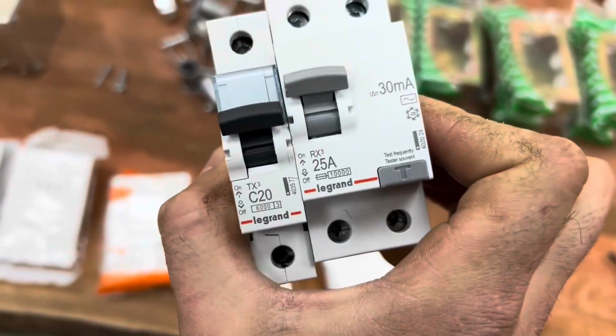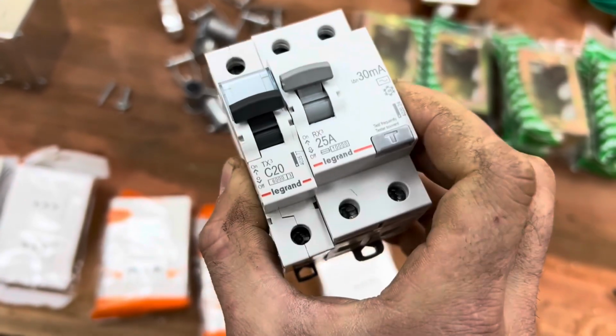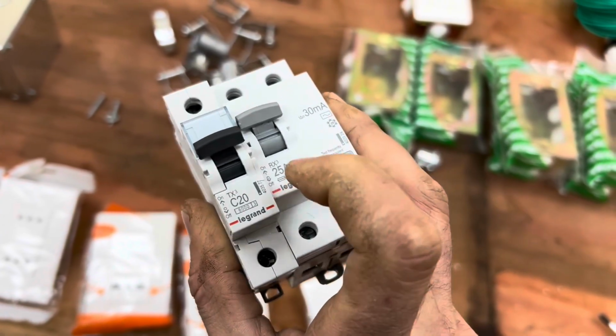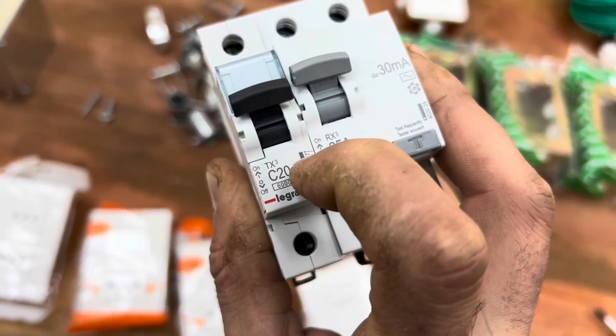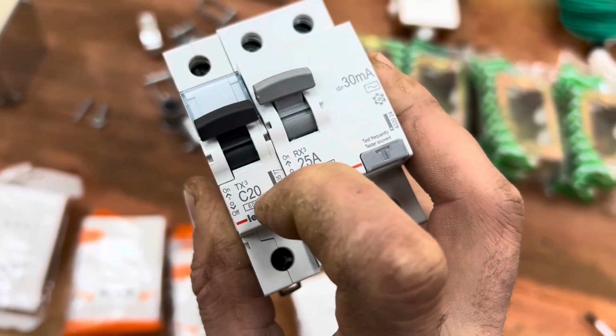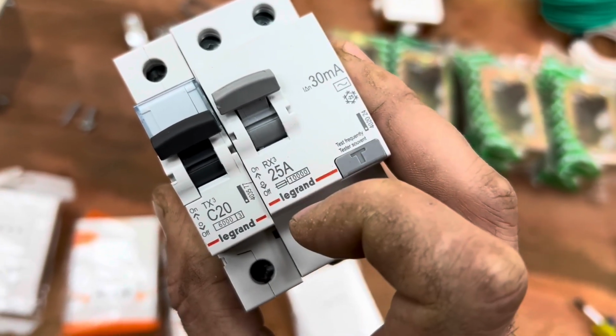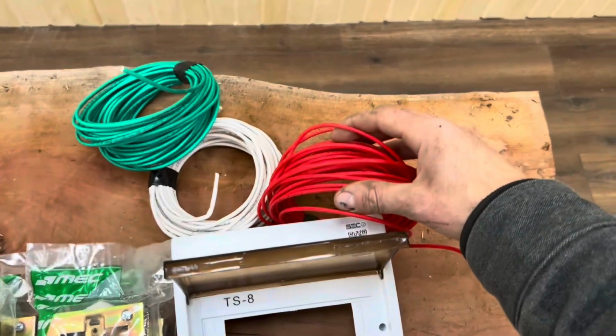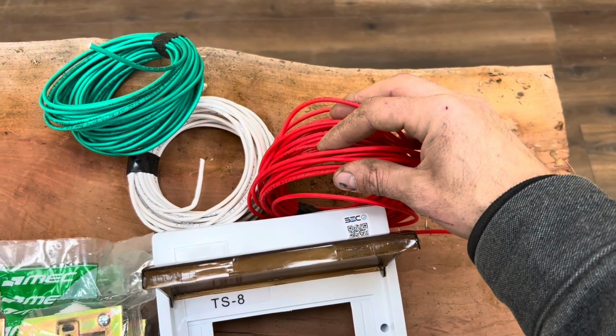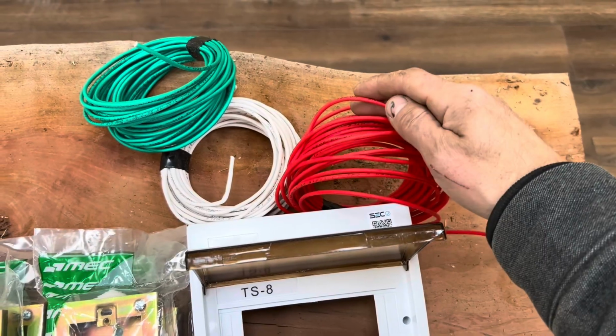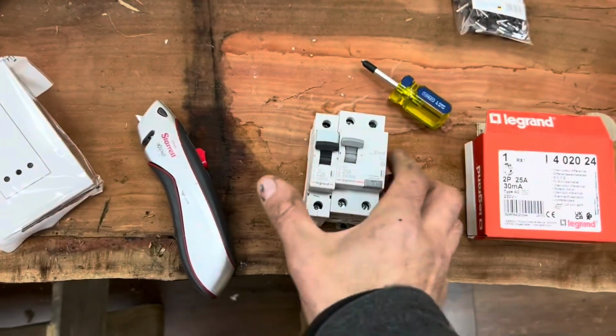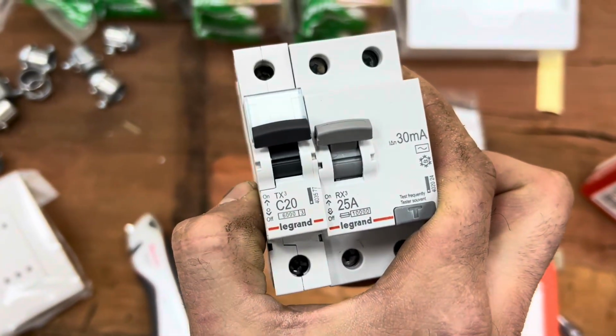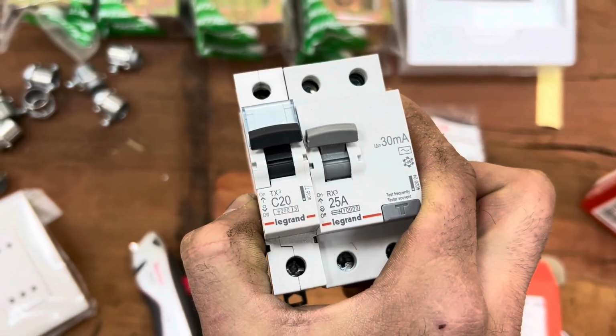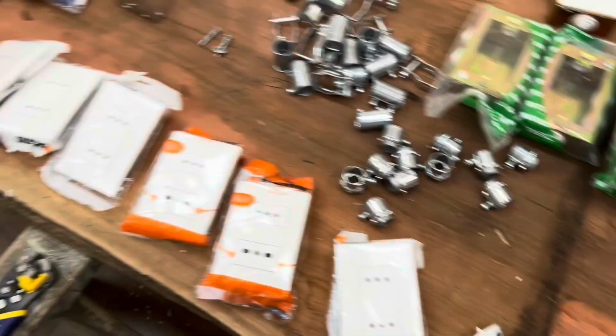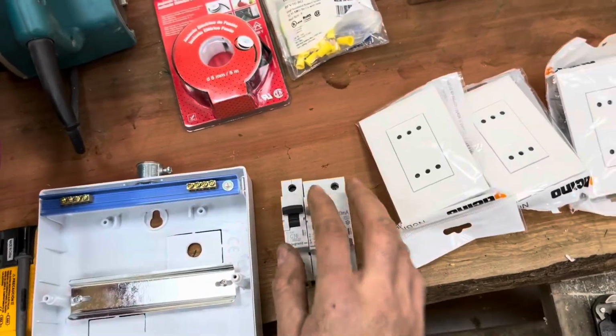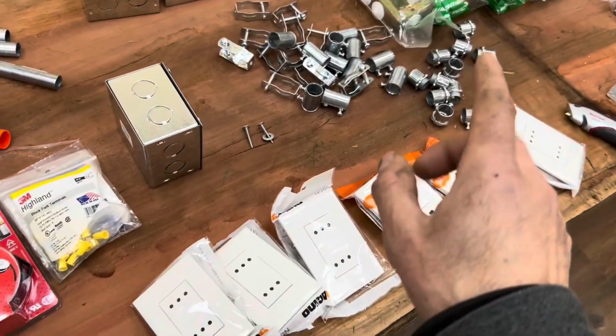Later on, we are going to bring in an edge bander and a planer, which are more powerful and need a bit more automation. In this case, we are going to use a 20 amp circuit breaker and its 25 amp residual current device. We are using a cable thickness of 2.5 millimeters, which will be more than enough for the use we're going to give it here in the workshop when I bring in the edge bander. I would like to be able to make the connection with a slightly thicker cable, 4 millimeters, but for now we'll only use the outlets from the 16 amp circuit so that 2.5 millimeter cable will be perfect.